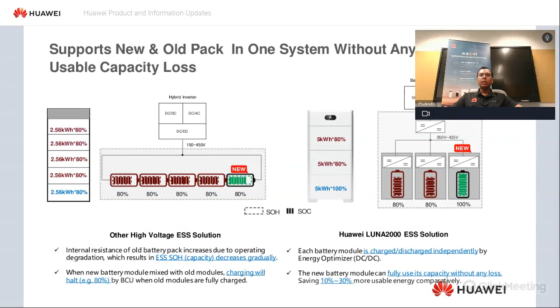Whereas in the Huawei Luna battery, each battery module works independently, parallel to each other. This symbol with the equal sign is the energy optimizer, and each module has one. So if we swap out a new module, it can perform at 100% efficiency even if the other modules are performing less than 100%, for example. That gives you at least 10 to 30% more usable capacity when you compare it like for like.